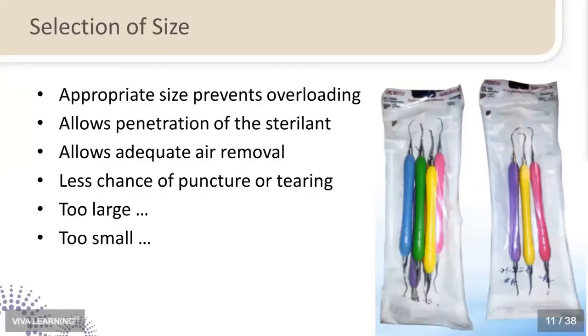It also, when you're using the right size pouch, allows the penetration of the sterilant. If you have too small a pouch, you may not be able to get enough of the steam inside the pouch to be able to access all of the instruments. So choosing the right size pouch is very, very important. Likewise, if you overfill the pouch or you're using a pouch that's too small, you may have trouble with air removal out of the pouch at the end of the cycle. And then you're going to end up with wet packs. So there's a number of things to be looking at, not only when you put the instruments into the sterilizer, but also when you take them out and look at the results.